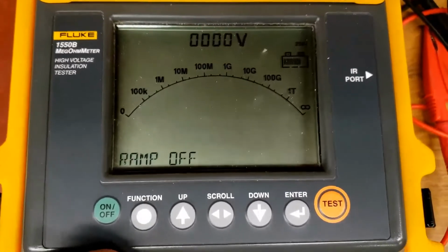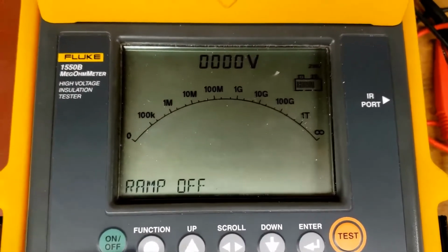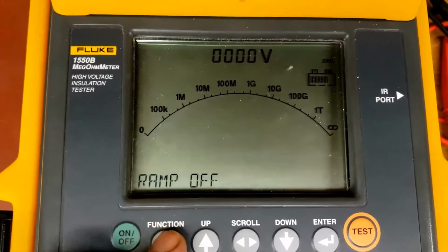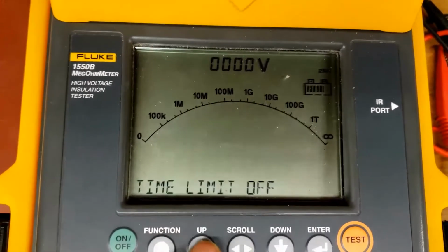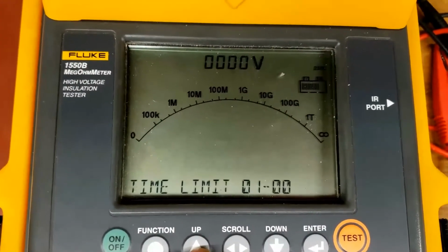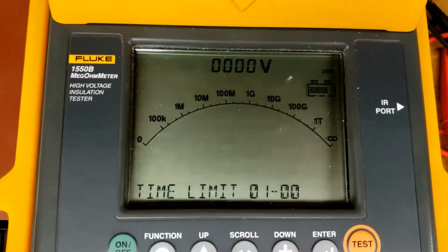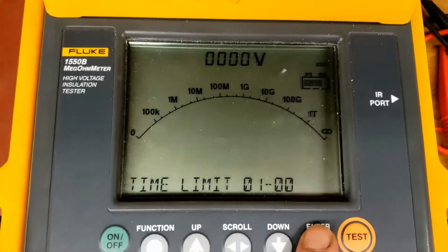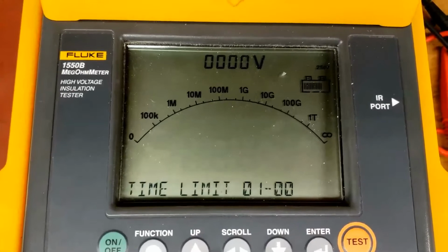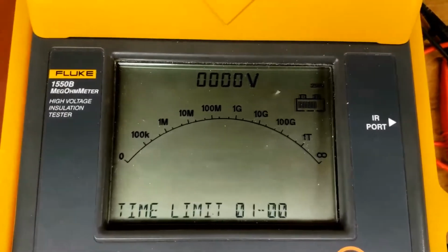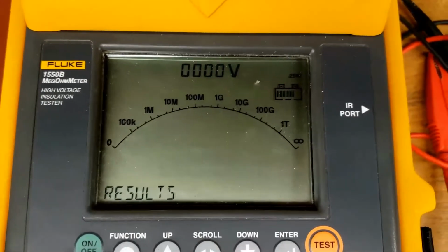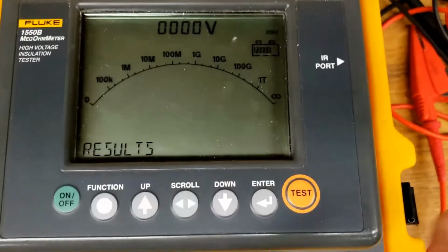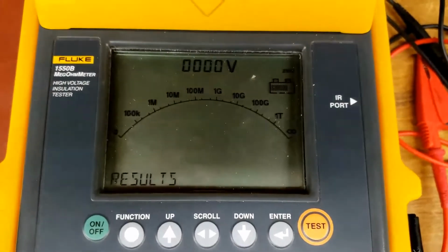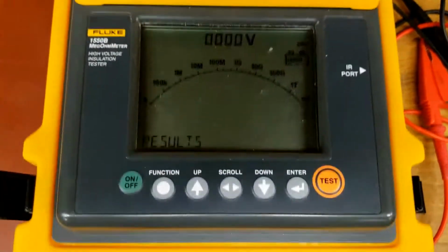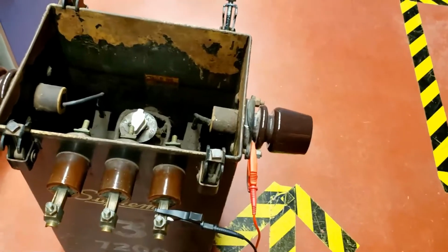Ramp means, does it bring the voltage up or does it just turn it on and hold it there? We don't want it to ramp, so that's off. Time limit, I can use the up or down arrows to change these values. So I want a 1 minute test. And then when we're done, we just press enter and go function to display results. Now I can hook it up to something, press test, it'll test it for 1 minute and give us an output. And I'll do that in a second.